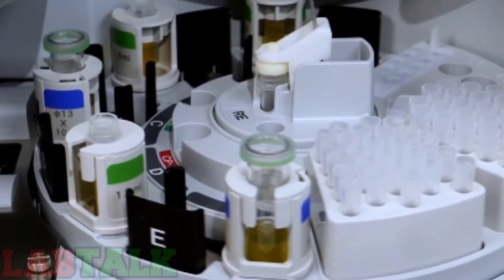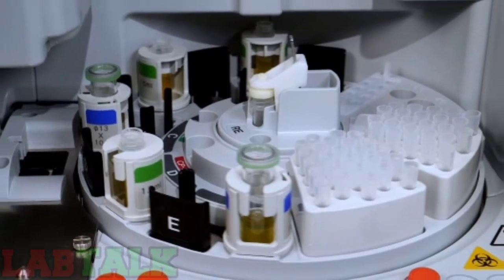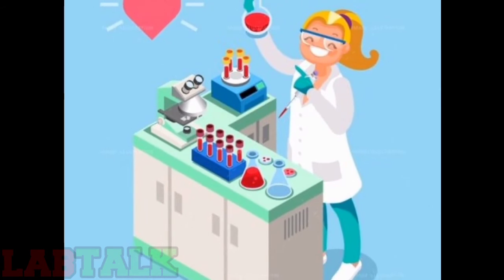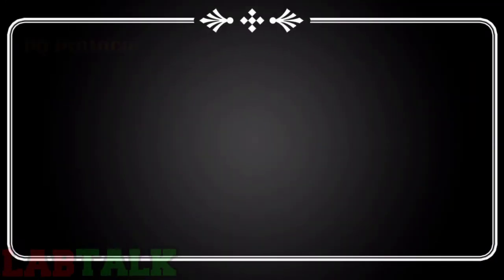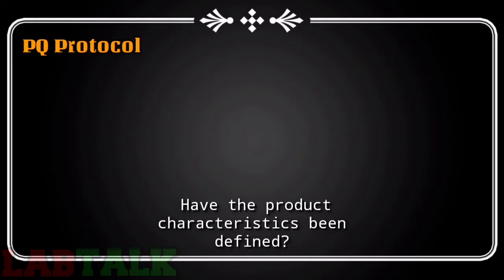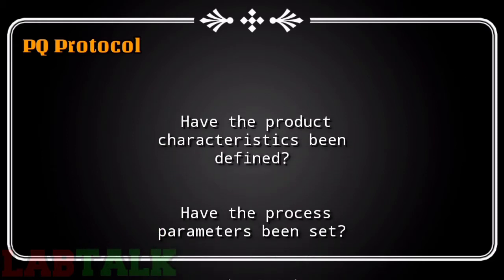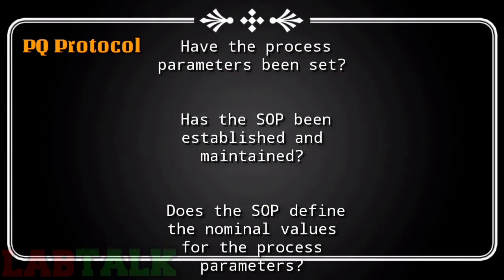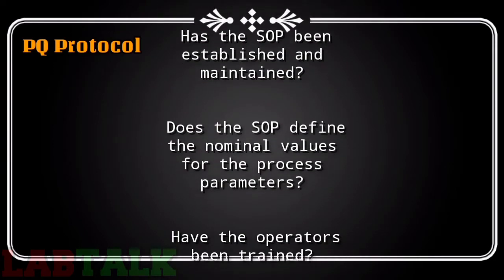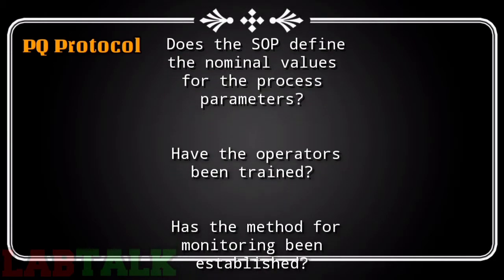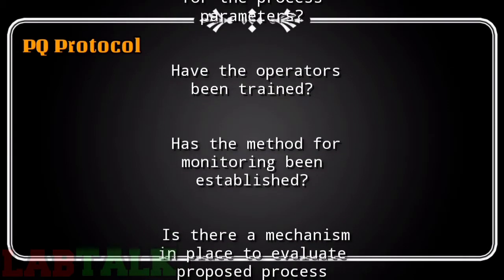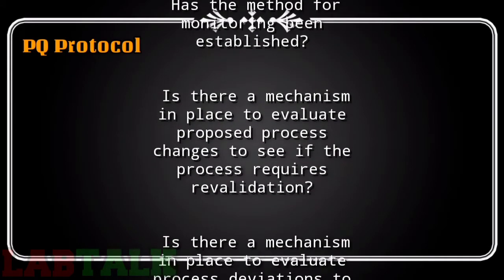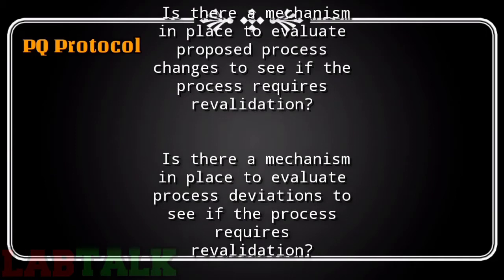Following checklist for the PQ portion of the process validations should be made available. This includes the following points: Have the product characteristics been defined? Have the process parameters been set? Has the SOP been established and maintained? Does the SOP define the nominal values for the process parameters? Have the operators been trained? Has the method for monitoring been established? Is there a mechanism in place to evaluate proposed process changes to see if the process requires revalidation? Is there a mechanism in place to evaluate process deviations to see if the process requires revalidation?